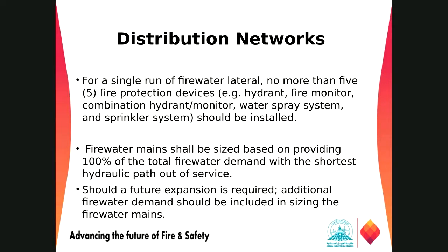And your fire water main shall be sized based on 100% of total demand, with the shortest hydraulic path out of service, right? Shortest hydraulic path out of service means we have to size our underground networks with hydraulic software. Keep in mind that in any case the supply line must provide the full demand at 100% design capacity.